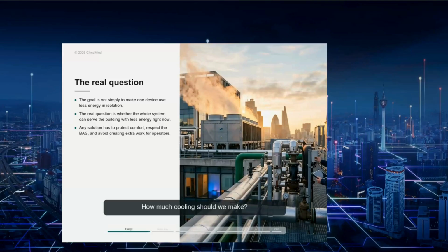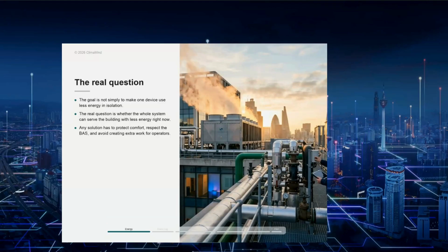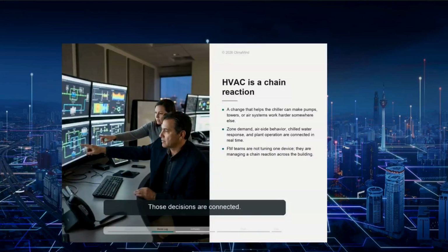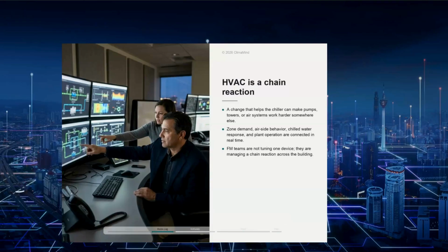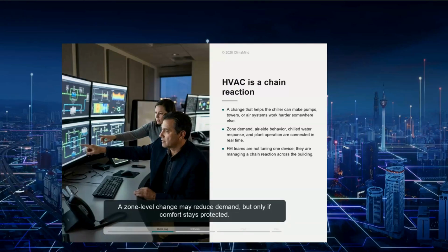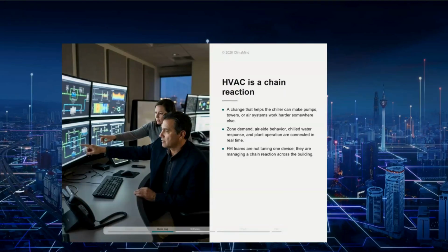How much cooling should we make? How much water should we move? How hard should the fans work? How much margin should we keep because the day may get warmer or the building may fill up? Those decisions are connected. A setting that helps the chiller may make the pumps work harder. A cooling tower decision may reduce one kind of energy but increase another. A zone level change may reduce demand, but only if comfort stays protected.